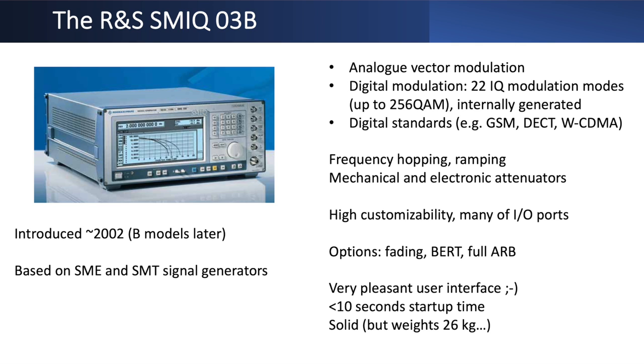So some of its main features are that we can do analog vector modulation. We can do digital modulation, and we have a choice from many different IQ modulation modes. And interestingly enough, these modes are really internally generated. Unlike many other IQ signal generators, where you first have to create the IQ signal in a separate software program, and then you have to transfer that data set into the device, and then it plays it as an arbitrary sequence, which is much more cumbersome. The nice thing about this device is that it really creates it out of the box. You do all the settings and it creates the IQ signals that you're interested in.